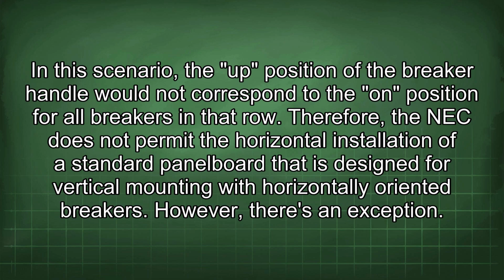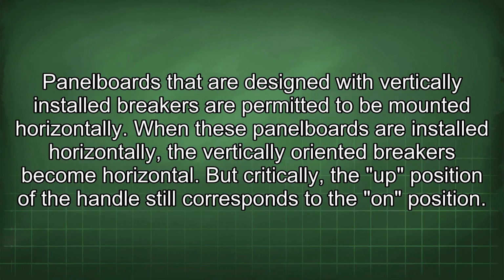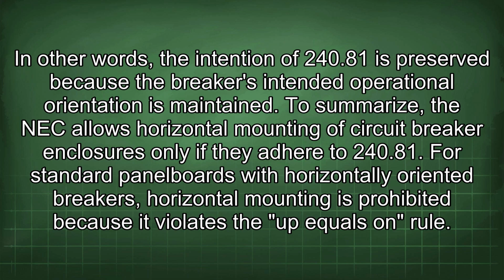Therefore, the NEC does not permit the horizontal installation of a standard panel board that is designed for vertical mounting with horizontally oriented breakers. However, there is an exception. Panel boards that are designed with vertically installed breakers are permitted to be mounted horizontally. When these panel boards are installed horizontally, the vertically oriented breakers become horizontal. But critically, the up position of the handle still corresponds to the on position. In other words, the intention of 240.81 is preserved because the breaker's intended operational orientation is maintained.